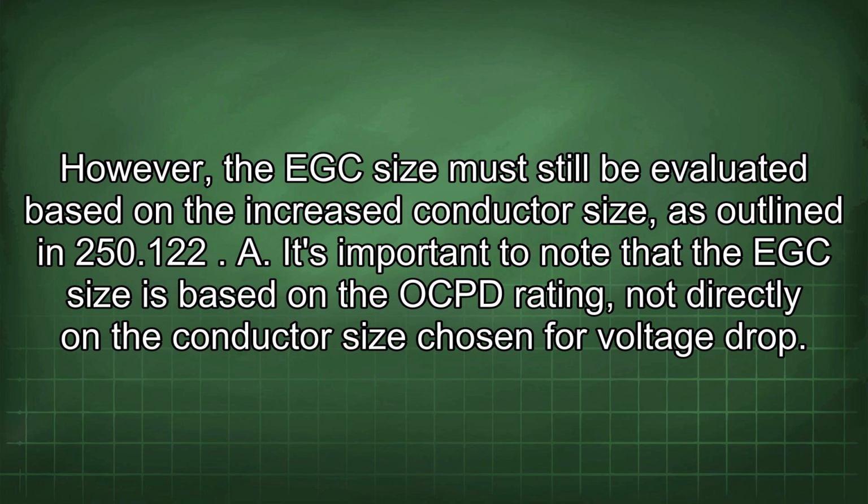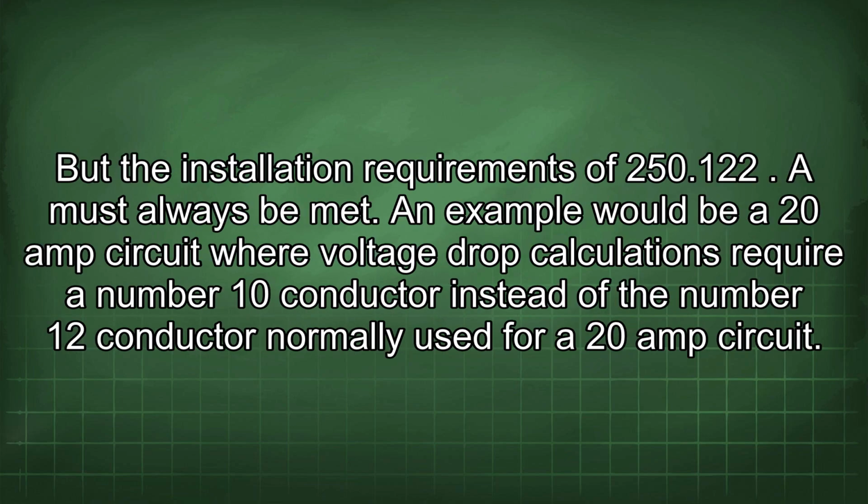in 250.122. It's important to note that the EGC size is based on the OCPD rating, not directly on the conductor size chosen for voltage drop, but the installation requirements of 250.122 must always be met.